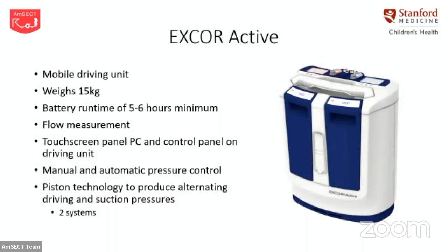And so next we'll go into the new active driver. It is much smaller and a mobile driving unit, only weighing 15 kilos, with a much longer battery runtime of a minimum of 5 to 6 hours. We are also able to now measure flow with the driver. And instead of the integrated laptop, you have a touchscreen panel PC.